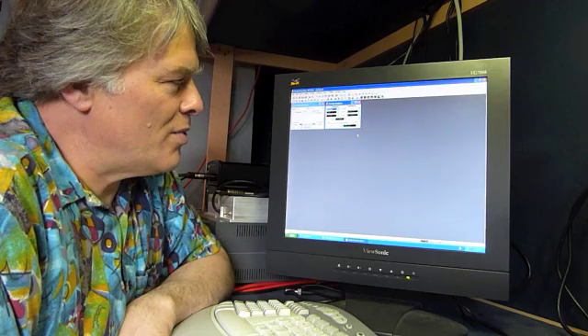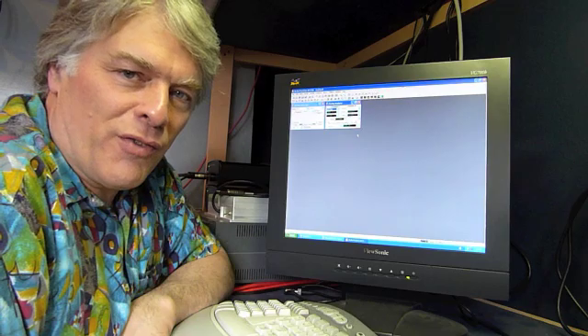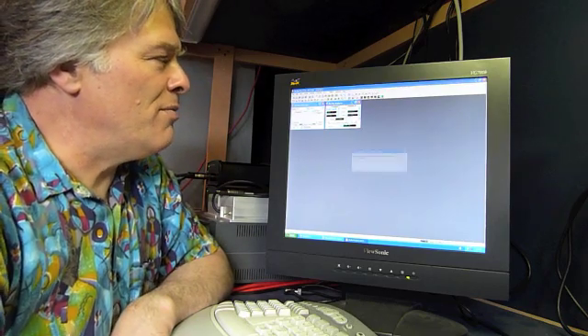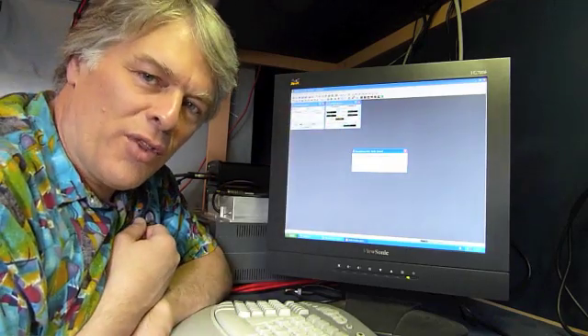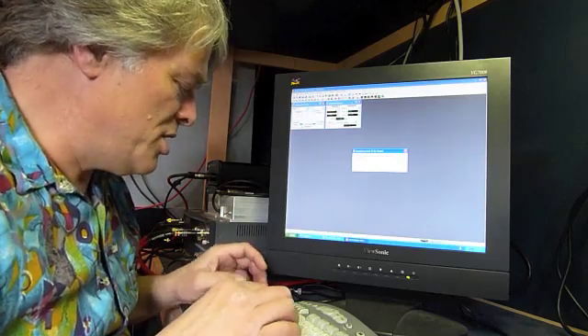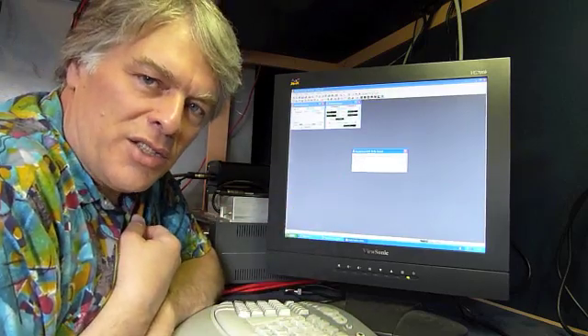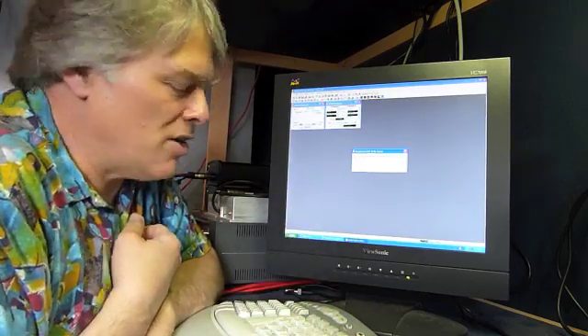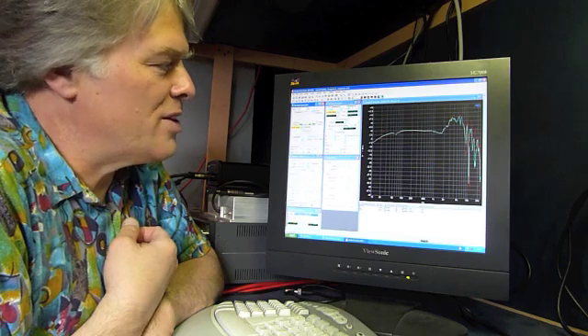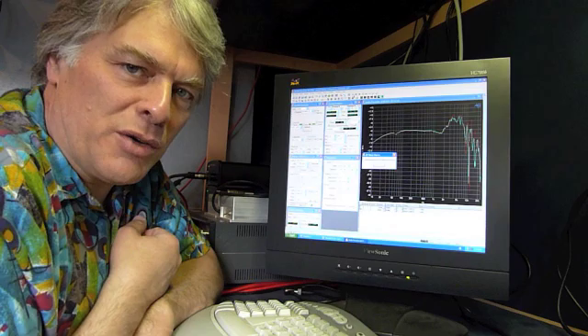You can hear the relays clicking there. It's just a blank test at the moment until the script begins to run and calls the first actual test. So I'm going to push the run button up here and it's going to ask me for the name of the headphone that I'm going to be testing. In this case, it's an AKG Q701. That information is going to be put onto the spreadsheet as the test carries on. I'll hit OK. Again, you can hear all the relays clicking and now it's set up the test panels for the frequency response test.